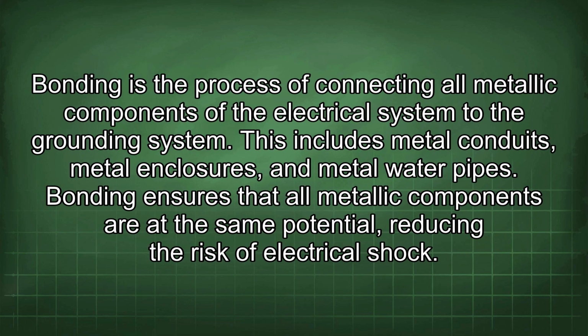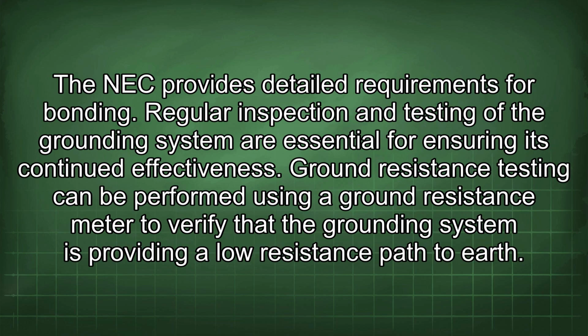Bonding is the process of connecting all metallic components of the electrical system to the grounding system. This includes metal conduits, metal enclosures, and metal water pipes. Bonding ensures that all metallic components are at the same potential, reducing the risk of electrical shock. The NEC provides detailed requirements for bonding. Regular inspection and testing of the grounding system are essential for ensuring its continued effectiveness. Ground resistance testing can be performed using a ground resistance meter to verify that the grounding system is providing a low resistance path to earth.